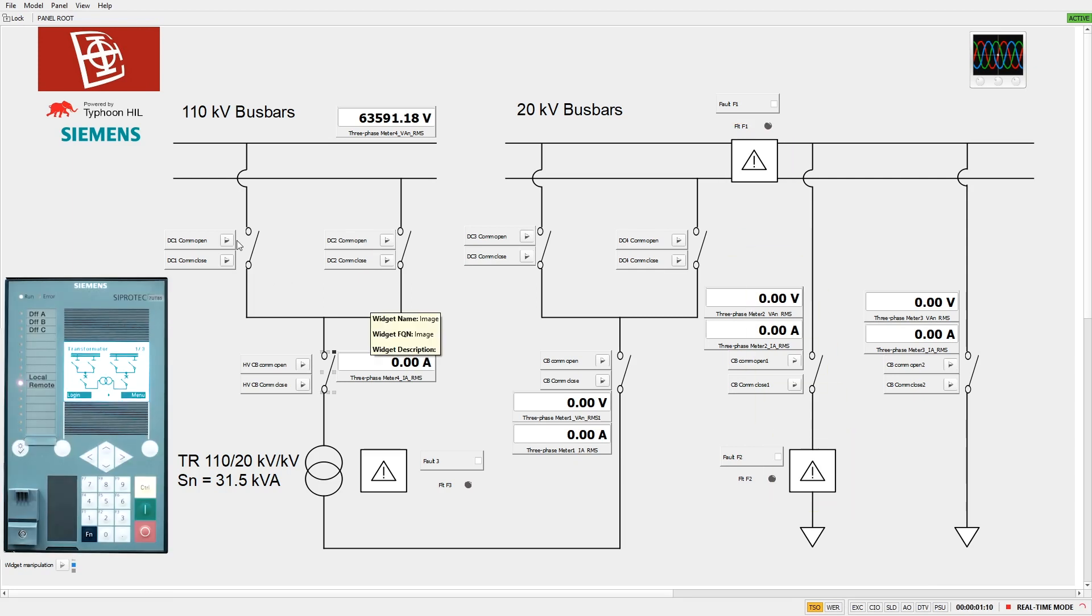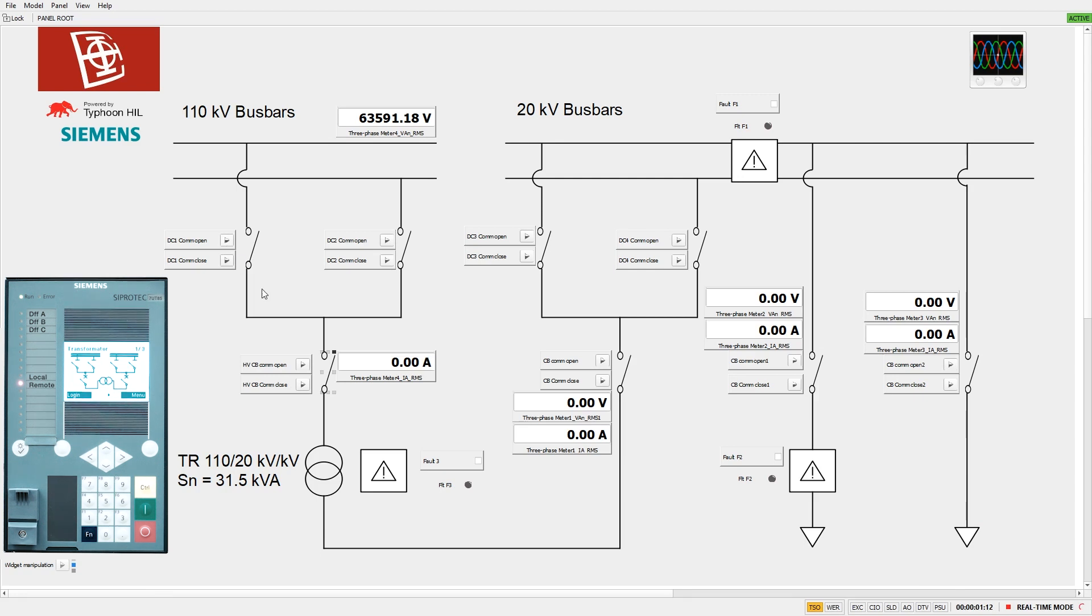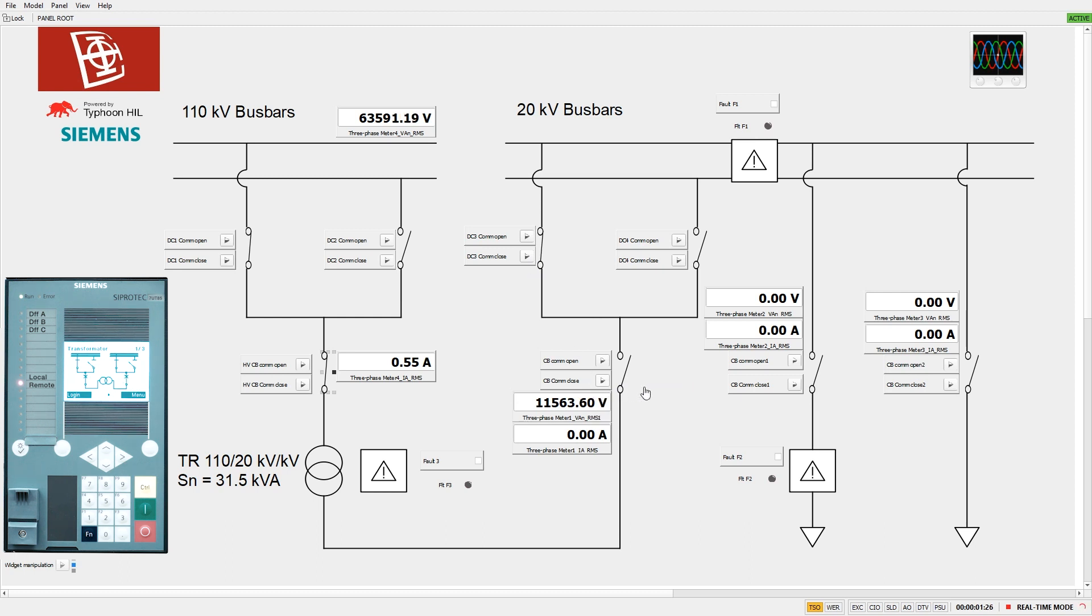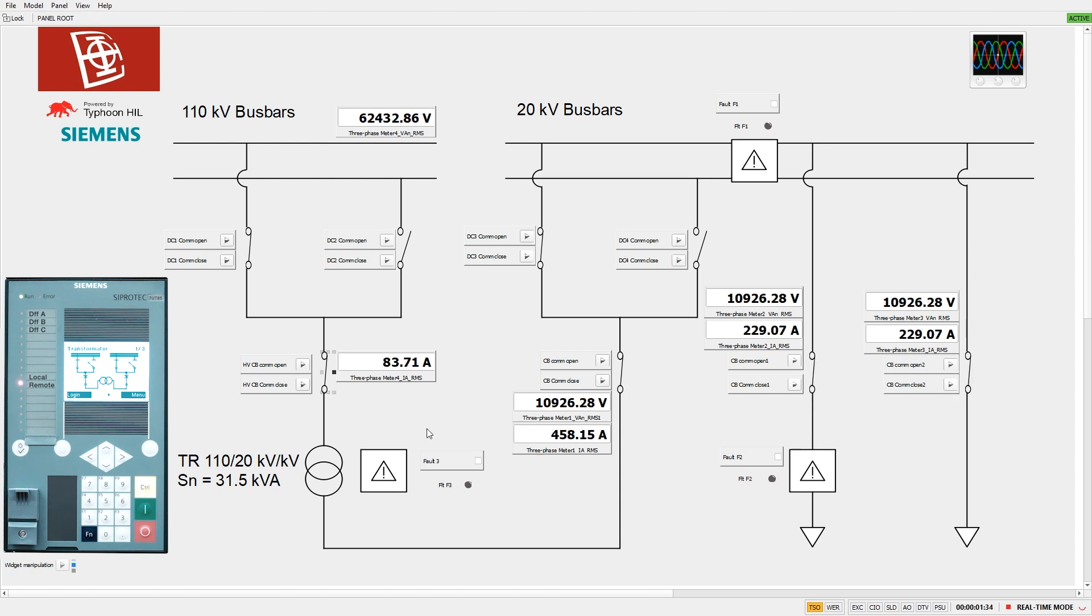During the simulation, the HIL 602+ device injects currents and voltages to the analog inputs of the high and medium voltage merging units via the HIL connect. The status of the circuit breakers is sent by GOOSE communication via the network switch. The merging units transmit data streams composed of sampled values to the 7UT85 differential relay, utilizing optical ports and the network switch.